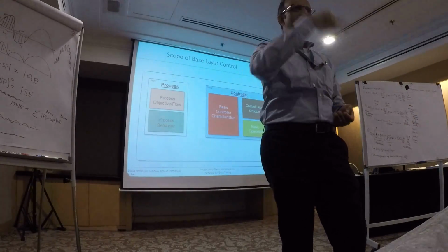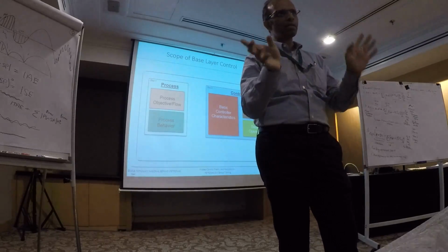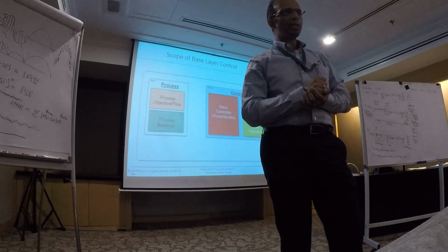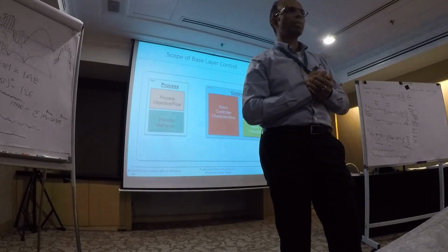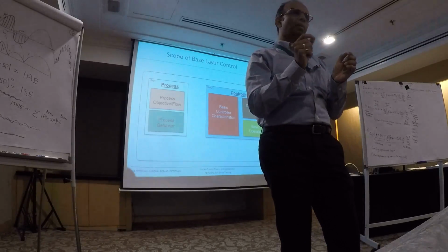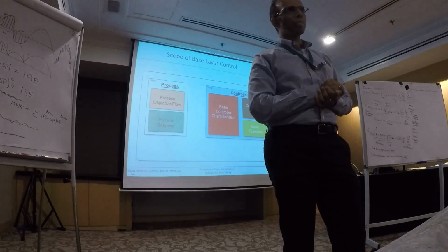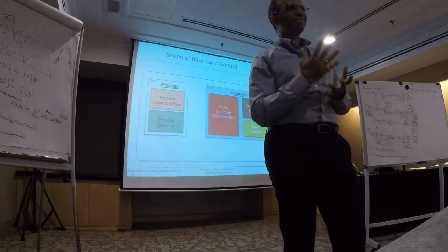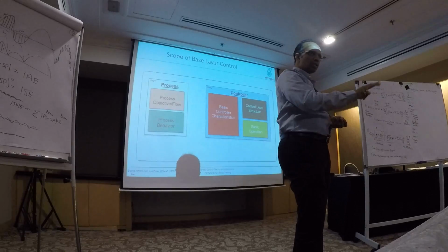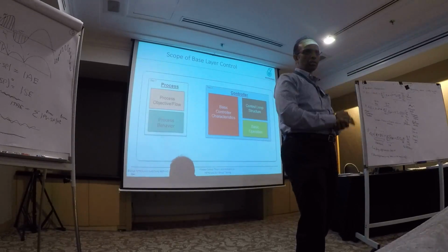It's very simple. I just did a sine curve and a random noise generator, superimposed them, and got my noise. I played with this many times trying to figure out the best way. But almost every one I used, when I increased the filter size, I started getting attenuation of my process. So that's why I instituted the rule for the fraternity: filter 3 seconds, I don't care what filter you use.